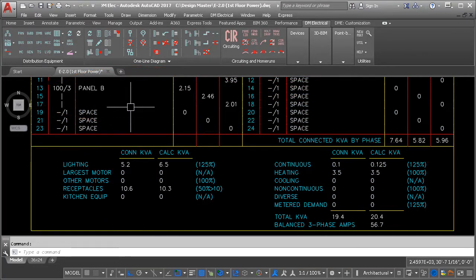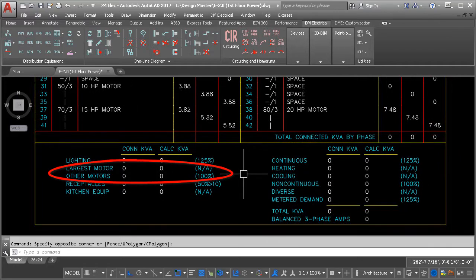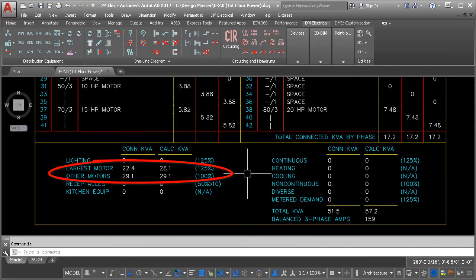The total load on the panel is calculated based upon NEC feeder and service calculations. Multiple motors? The software figures out which is the largest and adds 25% to its load.